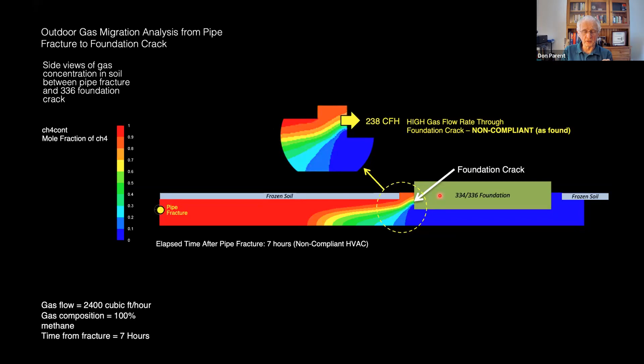And here's the result in the building. One of the guys actually created an Excel model of gas flow through the building to calculate, well, how did this manifest as gas concentration in the building itself? What was the gas concentration? And the reason for that is because it's important to know the gas concentration, because the susceptibility to ignition is related to the concentration of natural gas. And the LEL, which is the lower explosion limit for natural gas, is 5%. So if the natural gas concentration gets to be greater than 5%, it's explosive. If it's less than 5%, it won't explode.